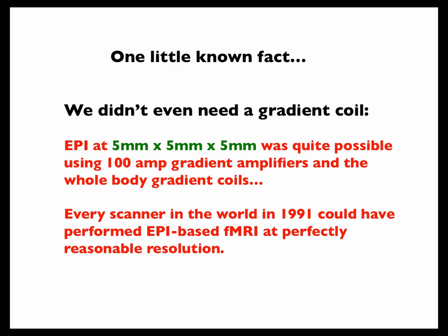We actually didn't need a gradient coil at all. And none of these groups actually could have really needed a gradient coil. You could have collected perfectly good data at 5 millimeter cubed without the gradient coil. You could do that on your standard 100 amp, really wimpy gradient amplifiers that they had at the time. Everyone could have been doing echoplanar imaging with their standard coils, collecting low resolution, but still functional MRI data, single shot echoplanar imaging.